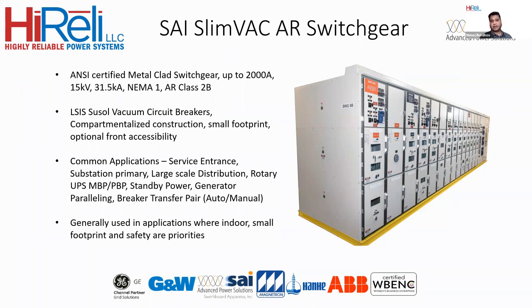They offer this as an option, meaning that the switchgear will come fully assembled on the skid before it leaves the factory. And this basically saves a ton of time and money in the field when the switchgear is being commissioned and installed. So there's a huge savings in terms of cost. And they can offer this across any of their product lines, so you can put low voltage gear on the skid as well. So it's a customized option, and it's something that can really contribute to cost savings in a project.